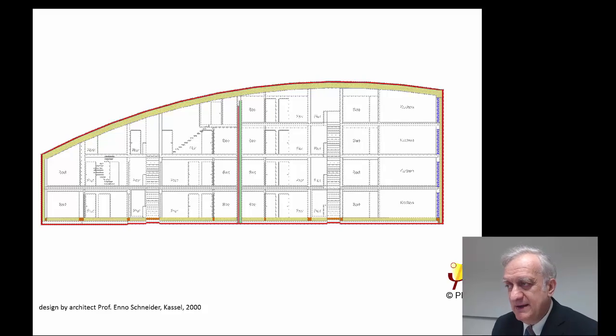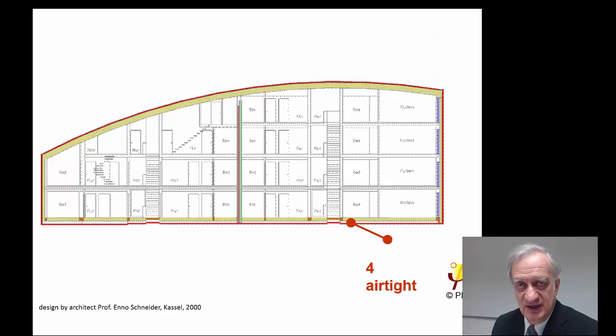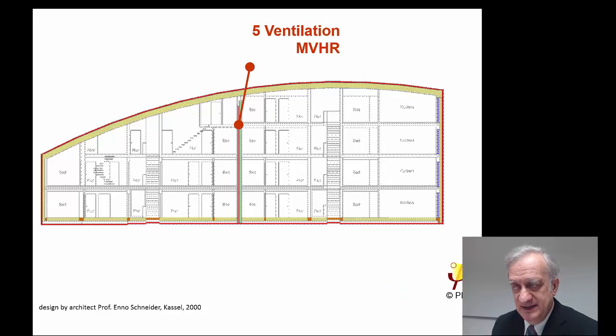How is that working? This is shown in a section of a typical multifamily Passive House, which was built by Professor Enno Schneider in the year 2000. What you see there is a very well-insulated building envelope that keeps the heat or coolness inside the building. It has to be free of thermal bridging and we use properly insulated Passive House windows. There is an airtight building envelope and the fresh air is supplied by a ventilation with heat recovery system.